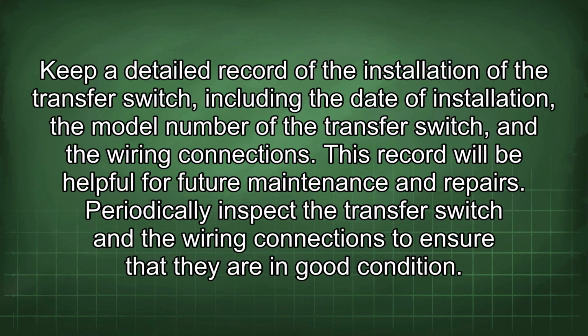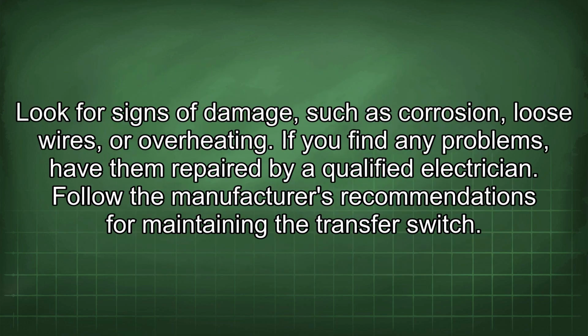Keep a detailed record of the installation of the transfer switch, including the date of installation, the model number of the transfer switch, and the wiring connections. This record will be helpful for future maintenance and repairs. Periodically inspect the transfer switch and the wiring connections to ensure that they are in good condition. Look for signs of damage, such as corrosion, loose wires, or overheating. If you find any problems, have them repaired by a qualified electrician.